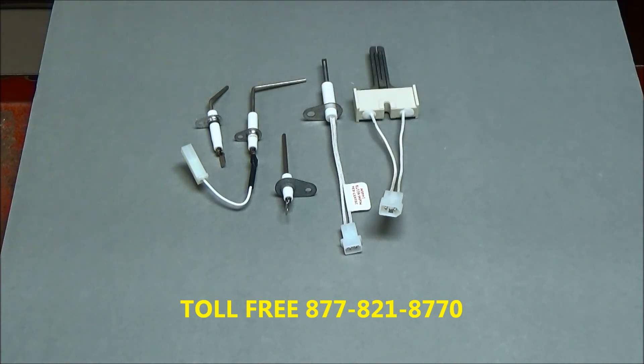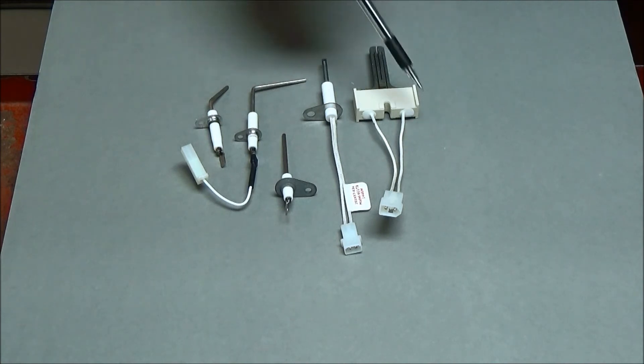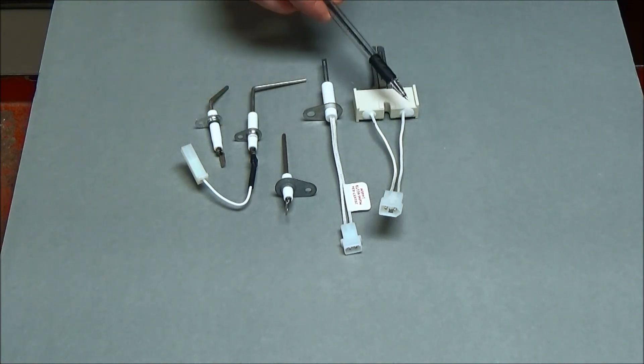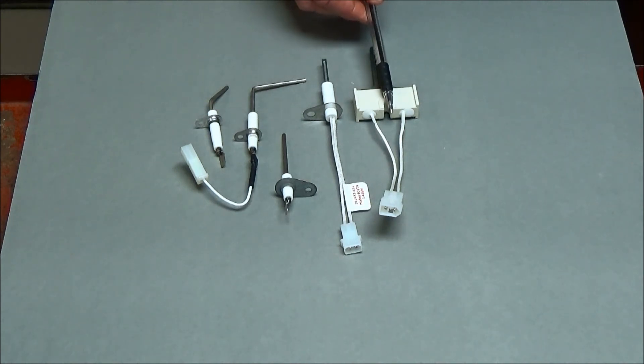Notice there's two wires to the igniter; there's one wire to the flame sensor. Leave your meter connected for the entire time the system tries. If you see voltage for a few seconds and then it shuts off, your igniter is bad. If you never see voltage, the problem is most likely the board.